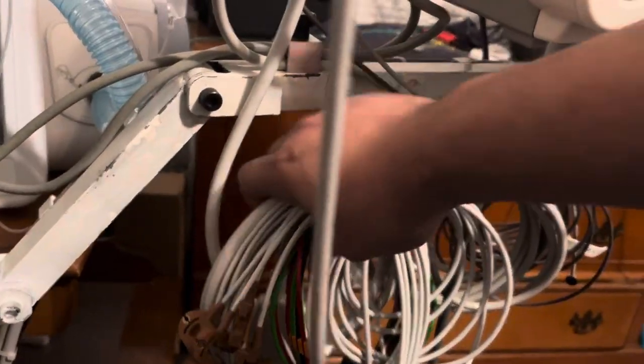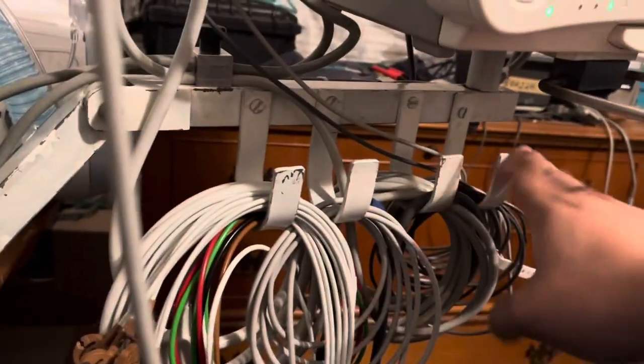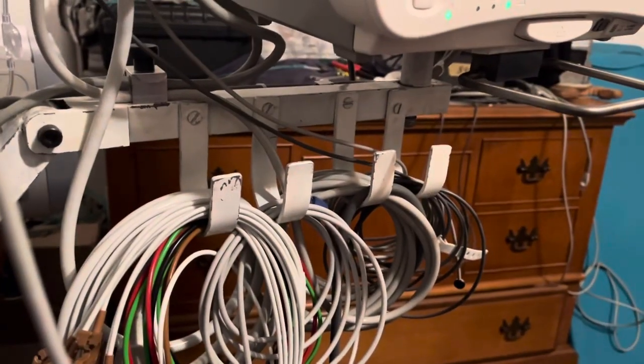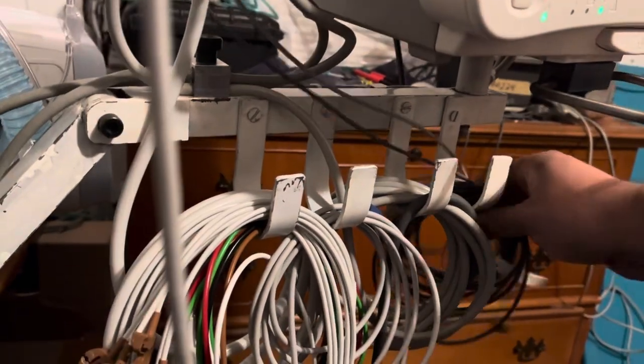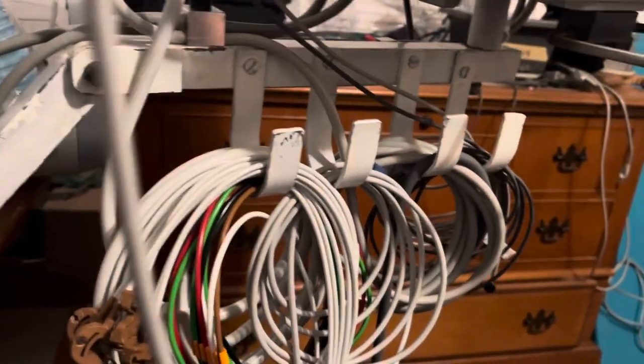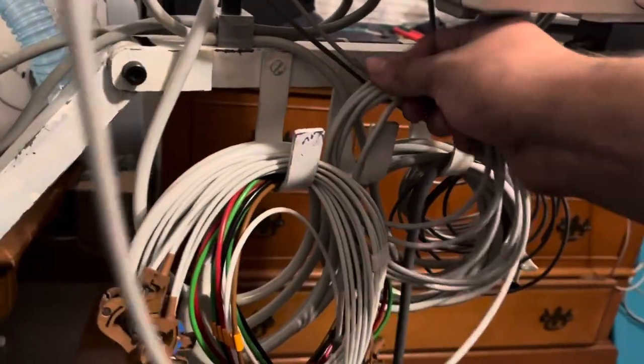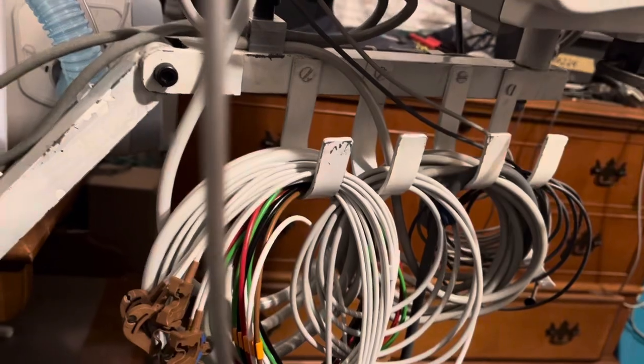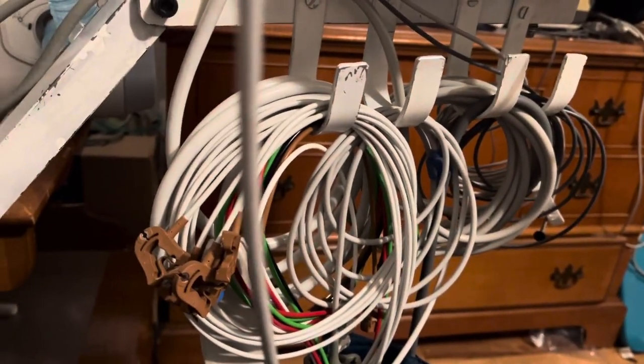Got ECG, so these hooks are also custom made. I made a jig to bend these out of aluminum. Everything got a white spray paint job, which is why it's kind of crappy, falling apart. But my 2 temp sensors, so rectal and skin temp, NBP, and I have a thigh cuff, the Masimo Rainbow sensor here, and the 10 lead trunk cable with the chest leads and the standard leads. And usually the chest leads are not here because I don't do 12 lead or 10 lead very often.